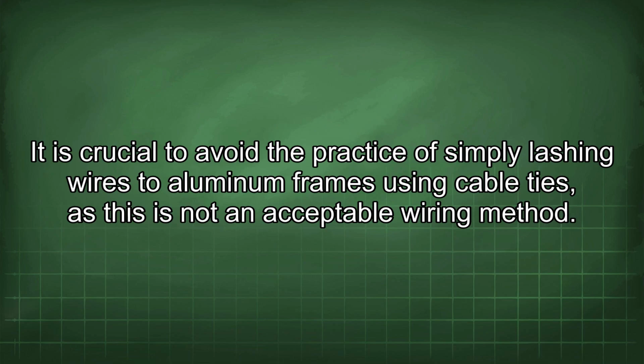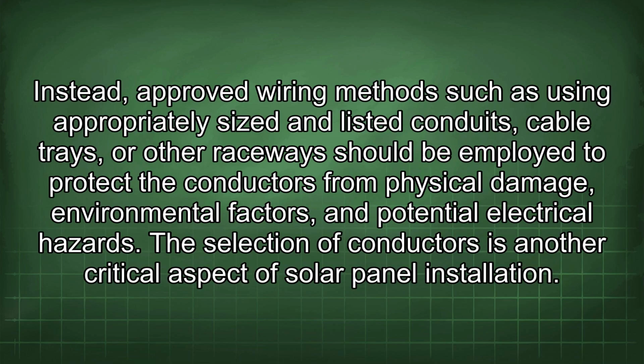It is crucial to avoid the practice of simply lashing wires to aluminum frames using cable ties, as this is not an acceptable wiring method. Instead, approved wiring methods such as using appropriately sized and listed conduits, cable trays, or other raceways should be employed to protect the conductors from physical damage, environmental factors, and potential electrical hazards.